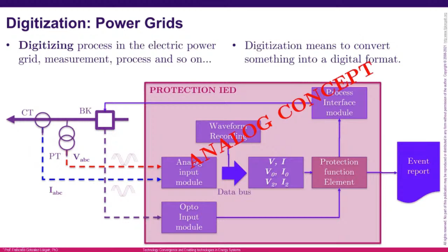Right now we are moving to digital substations, and the concepts are changing a lot. We are making the electrical signals, voltages and currents, digital, using a technology called non-conventional instrument transformers. These non-conventional instrument transformers can automatically convert the analog signal coming from the power system, voltages and currents, and they are converted into a digital data stream.